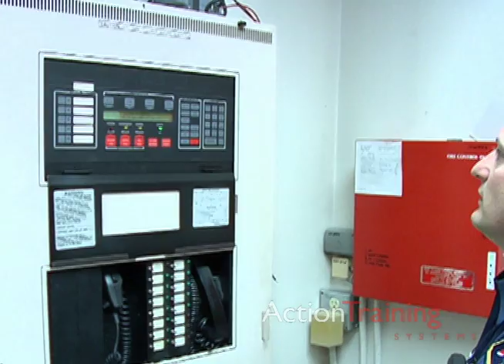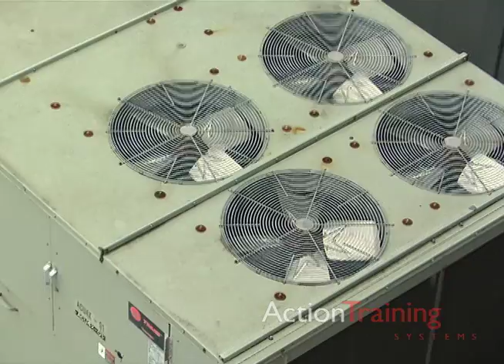In some facilities, the control panel activates auxiliary systems to increase life safety or to limit the damage caused by fires. For example, it may shut down exhaust or heating and air conditioning systems to control smoke, shut down processes or equipment, release building closure mechanisms, pressurize stairwells to aid with evacuation, activate fixed fire suppression systems, close fire doors and dampers, and monitor fire pumps and generators.